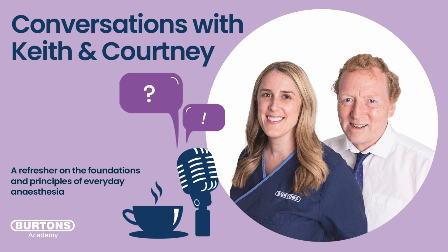So you get a flat line across the top of the trace, and then you just do it for about half a second and let go, and it drops down again, and it will overcompensate and go below the baseline that you had before, and then you get a little bit of what we call ringing. It will go right down, and then it'll come back up again, and then go back down and back up, and then it should level flat. And then you should pick up another pulse because you've left it in the line. And that's what we call the flush test.